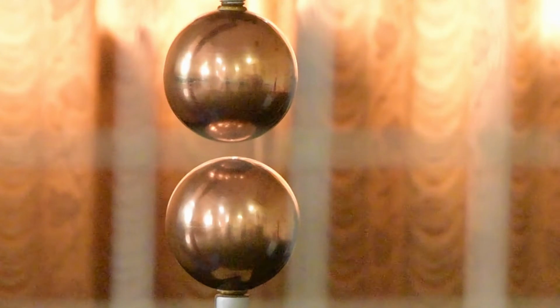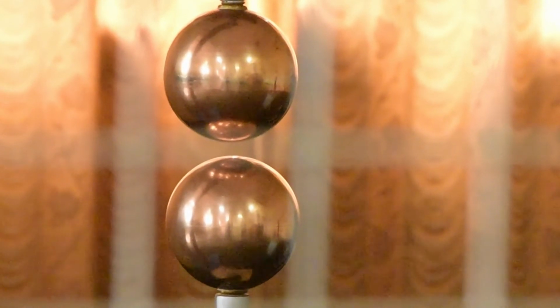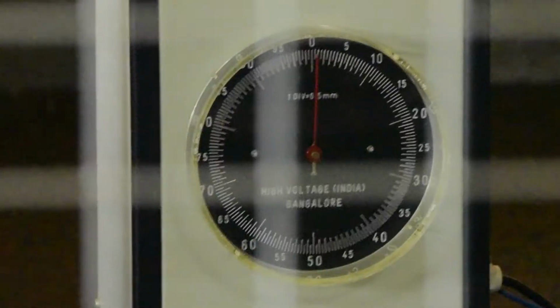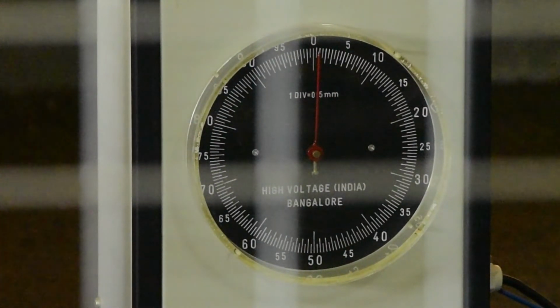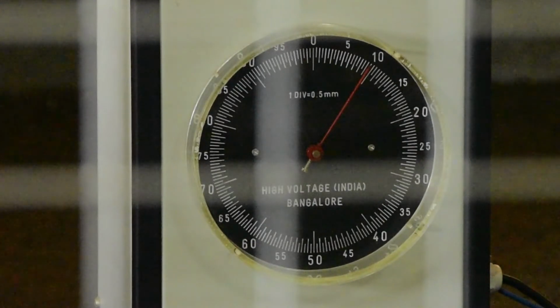Now we are going to check the same setting that is visible from the dial, which can be seen from outside the cage itself. Let us observe that. Let us check the same phenomenon as we adjust the spacing between the electrodes. You can see that gradually, as the spacing changes, it is reflected by a large dial. We are observing this dial from outside the cage itself. We are setting the spacing to 10 millimeters, and you can clearly see that 10 is written on the dial. So the spacing is now set. Now that the standard spacing is set between the 2 electrodes, we are going to go through the procedure to find the spark over voltage.